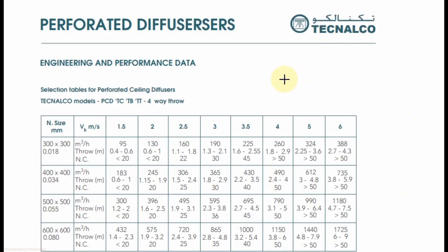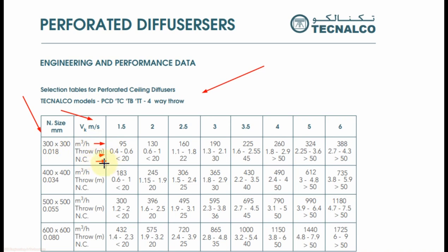This performance sheet is for selecting the 4-way type perforated ceiling diffuser. The first column shows the neck size in millimeters, and the top row shows the neck velocity in meters per second. The boxes in between show, for each size, the airflow in cubic meters per hour, throw in meters, and NC level. From any box you can select the airflow, throw, and NC level as per your requirement, then select the corresponding neck size of the perforated ceiling diffuser.